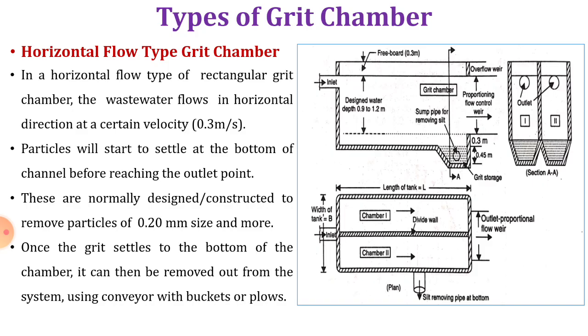The first type is the horizontal flow type grit chamber. As the name suggests, it is a rectangular channel where flow is horizontal. Because of the longer chamber, velocity is reduced as travel time increases; as velocity reduces, grit or inorganic material in the wastewater starts settling at the bottom. By this mechanism the grit settles in the hopper or grit storage and is disposed of safely. The wastewater flows horizontally at a velocity of about 0.3 meters per second, and particles start to settle at the bottom before reaching the outlet point.